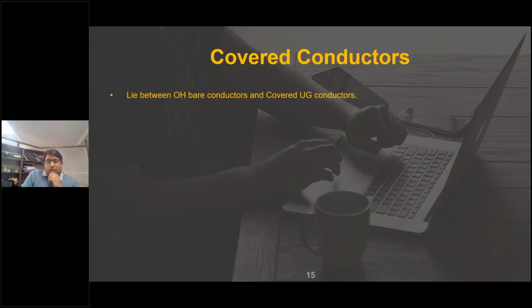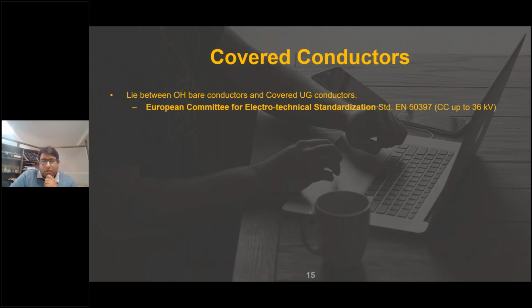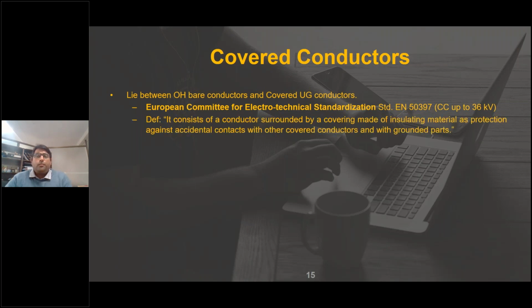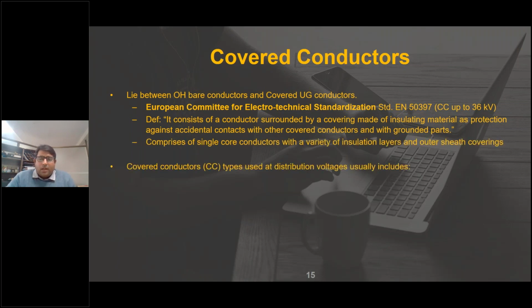So the covered conductor is a trade-off between overhead bare conductors and covered underground conductors. As per the European Committee for Electrotechnical Standardization, EN 50397 gives the limit of covered conductor up to 36 kV. As per the definition, it consists of a conductor surrounded by a covering made of insulating material as protection against accidental contacts with other covered conductors and with grounded parts. So it comprises a single core with a variety of insulation layers and outer sheath coverings.